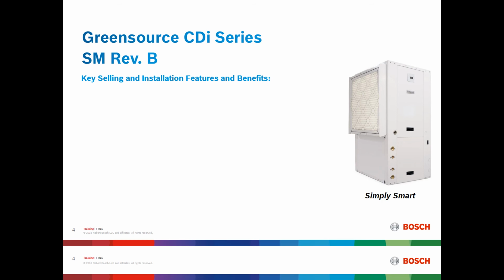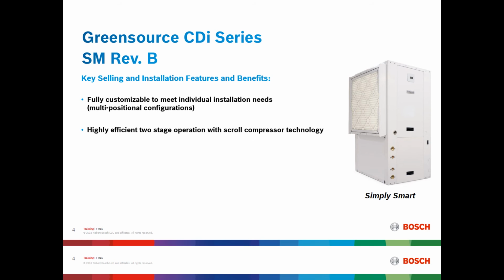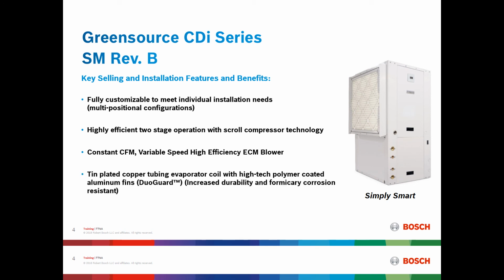The SM Rev B also has additional key selling and installation features and benefits, including being fully customizable to meet individual installation needs with a multi-positional configuration. Additionally, we offer a highly efficient two-stage operation with scroll compressor technology. The machine has a constant CFM variable speed high efficiency ECM blower and a tin-plated copper tubing evaporator coil with high-tech polymer-coated aluminum fins, referred to as DuoGuard, which increases the durability and formicary corrosion resistance. Finally, the SM Rev B is extended range capable, or commonly referred to as geothermal ready.